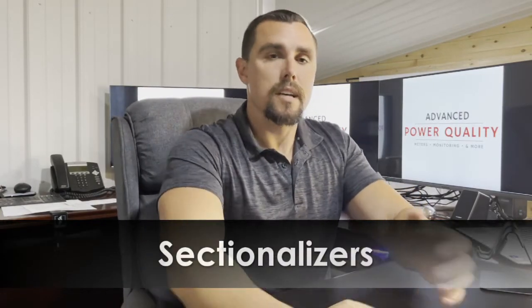What I mean is, our typical troubleman gets a call, or dispatch gives them a call—hey, these people are without power. The troubleman goes behind that fuse, that lateral line, and starts patrolling for issues, looking downstream from that fuse, when in reality the issue can be upstream. This next item: sectionalizers.